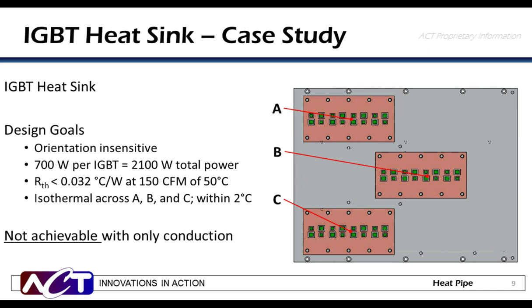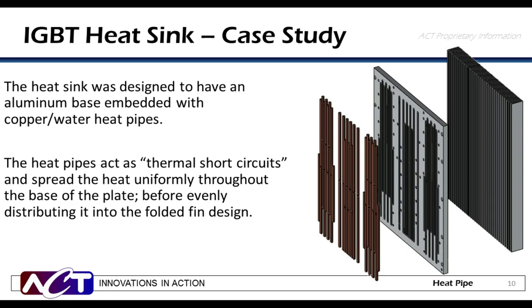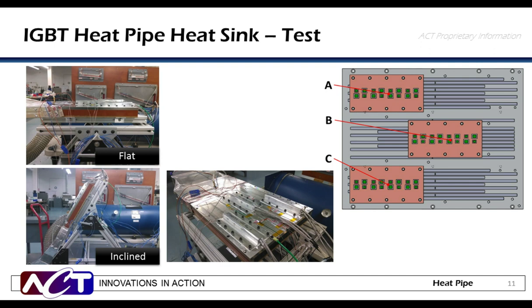Doing some basic analysis, you'll find that this is not achievable with conduction alone. That's where we look to a heat pipe embedded heat sink. This heat sink is designed with an aluminum base with embedded copper-water heat pipes. The heat pipes act as thermal short circuits, spreading heat uniformly throughout the base before it's spread into the folded fin design on the other side and dissipated to air. The grooves have been milled out, heat pipes embedded, and solder filled over top to ensure a smooth mounting surface for the IGBTs.